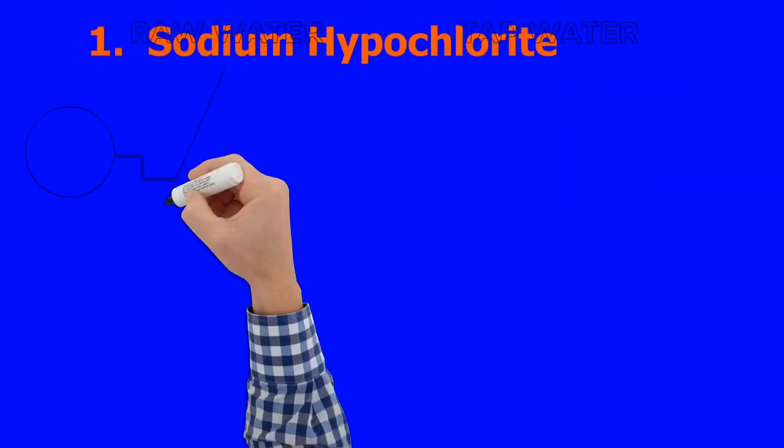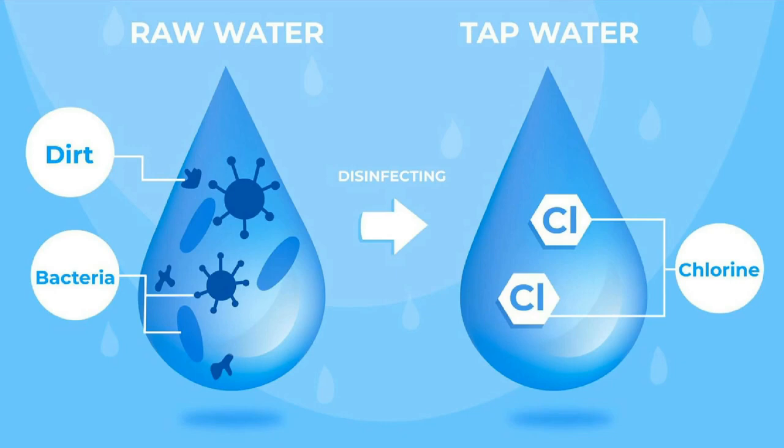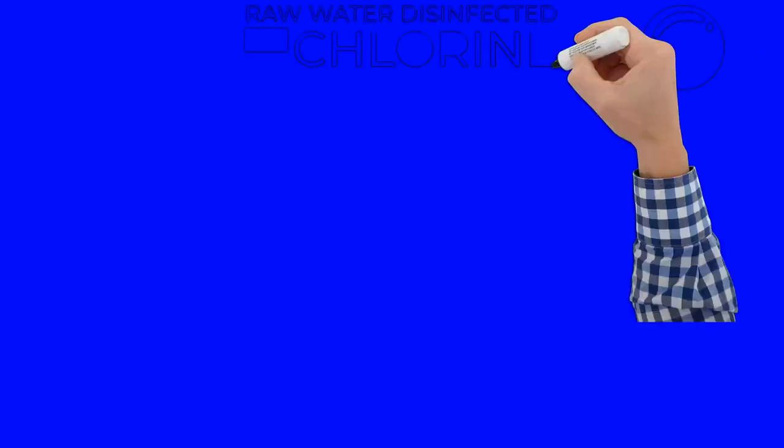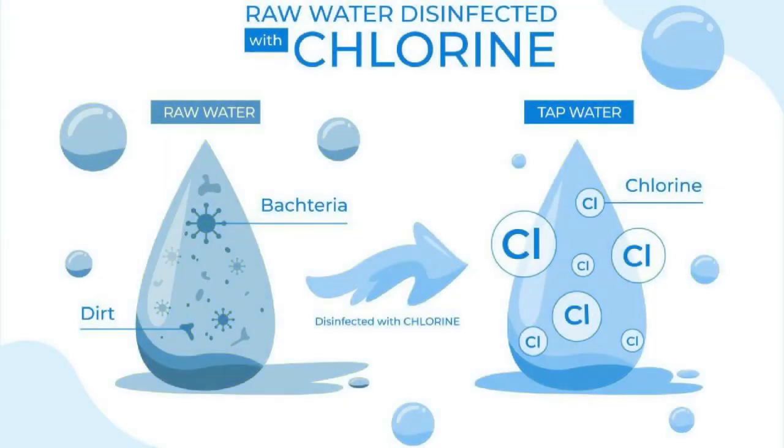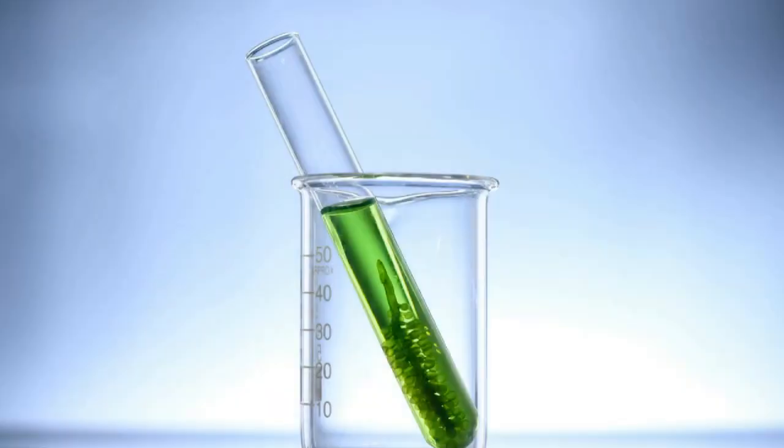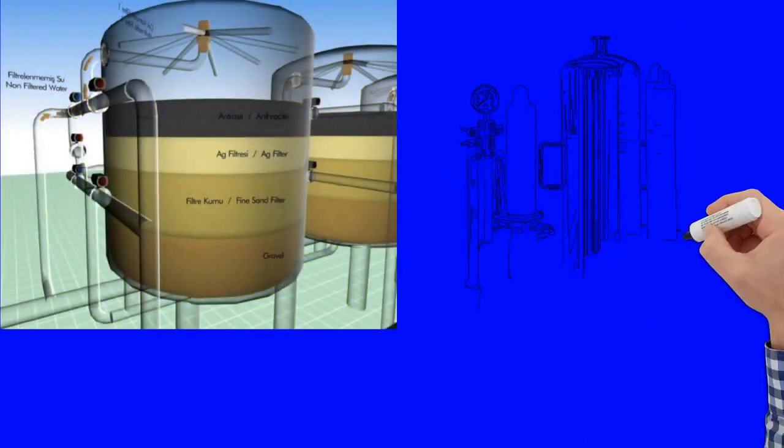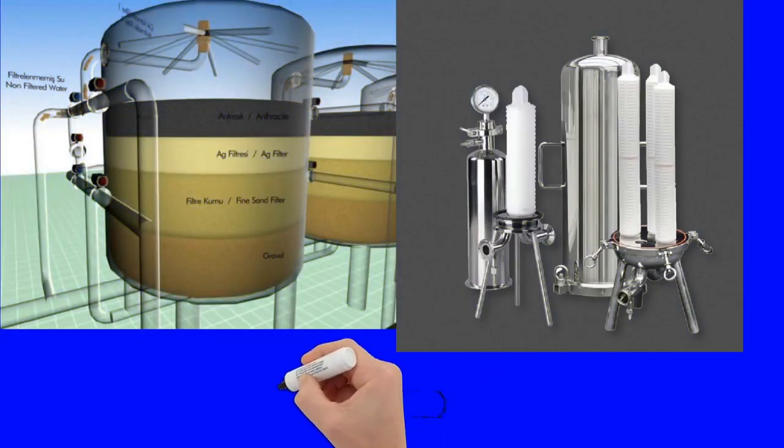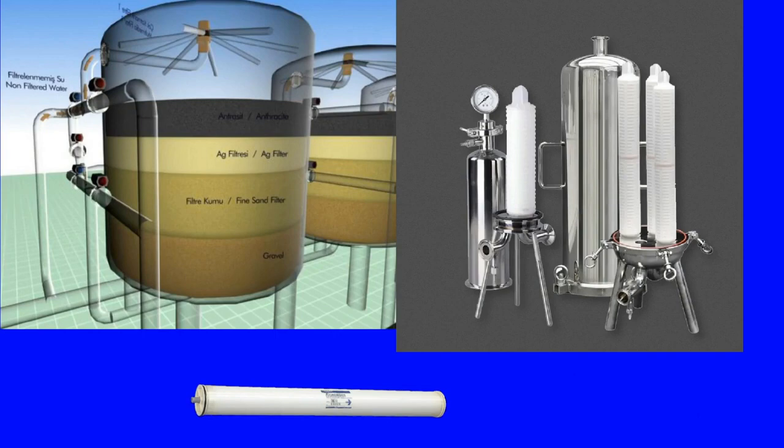Sodium hypochlorite is used for disinfection or chlorination of water. It can be used in two places: first in the raw water and second in the product water. The purpose of using sodium hypochlorite in the raw water is to avoid biological scaling in the multimedia filter, cartridge filter, and RO membranes.